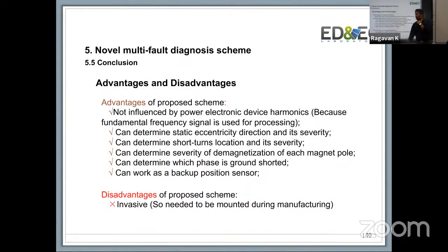So the challenge, of course, was that it's an invasive technique, which means you had to crack open your motor to install it. And that actually is a deterrent. A lot of companies don't want to crack open the motor because they don't manufacture it themselves. They have an external supplier who manufactures it, and opening the housing could actually create problems. So that is indeed a consideration that you have to take into account.